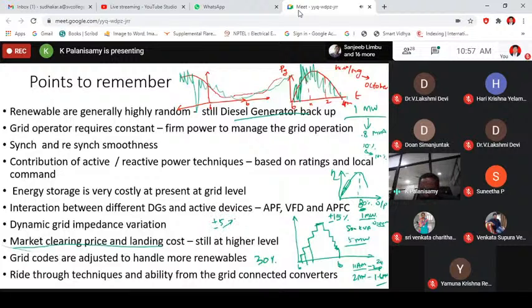It depends on the grid code, right? Even if it is increased, plus or minus 2%, 5 plus 2 or 5 minus 2, something like that. Also, earlier the frequency change was plus or minus 0.5%. Now this is also increased to the higher side as well as the lower side, to handle the renewables, right? Because more and more renewable penetration is expanding the variation levels, the boundaries. Only then can we operate.